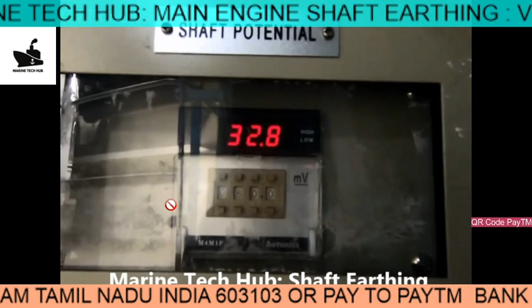If this is not happening, the current will take the path through the bearing. We have the main bearing, and this millivolt potential will start jumping through the bearing, causing a lot of pitting marks. To take care of the bearing, this shaft earthing is very important. I will show you the video now.